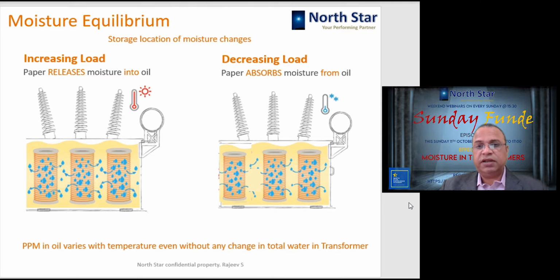What does that mean? If no water is coming in from outside, the insulation is not aging, and because of aging no additional moisture is being generated, then whatever water is inside the transformer is just getting shifted, so the concentration in the oil is going to vary depending upon the temperature of the transformer.